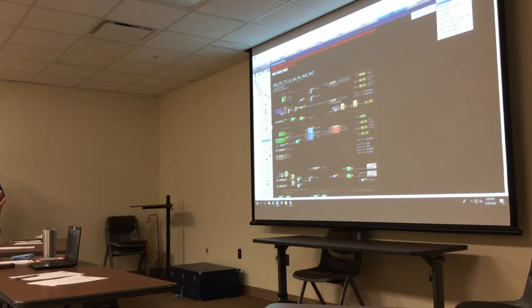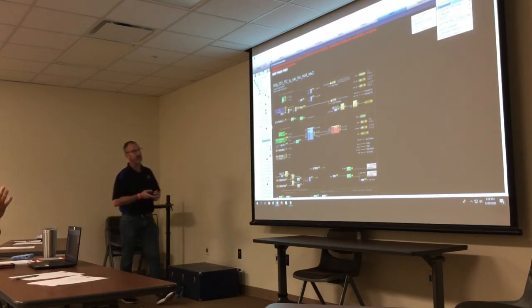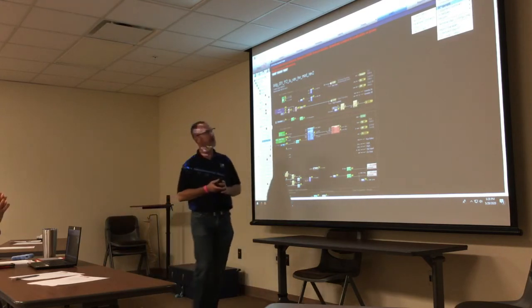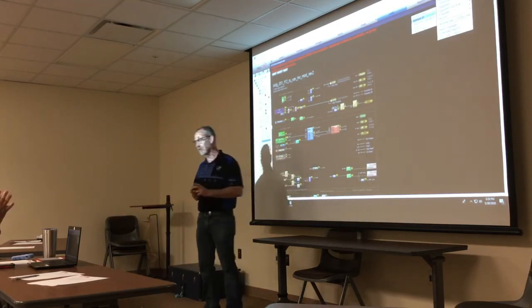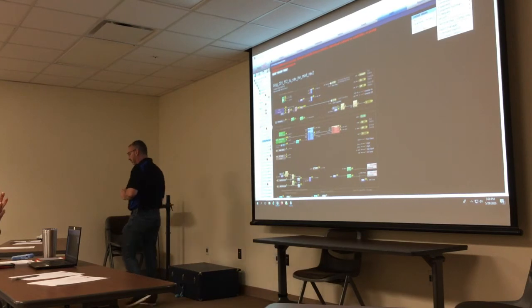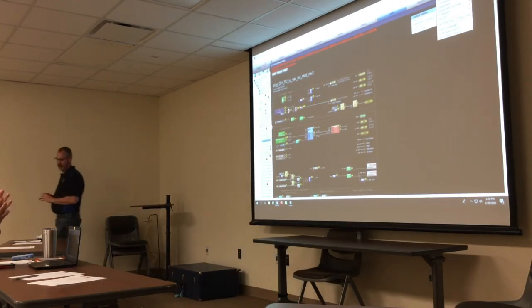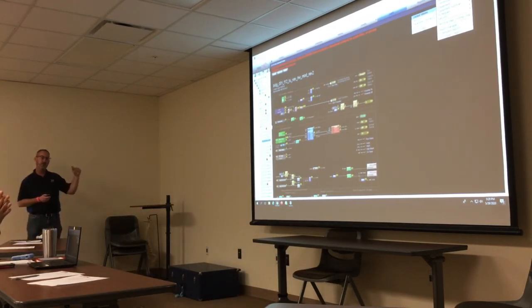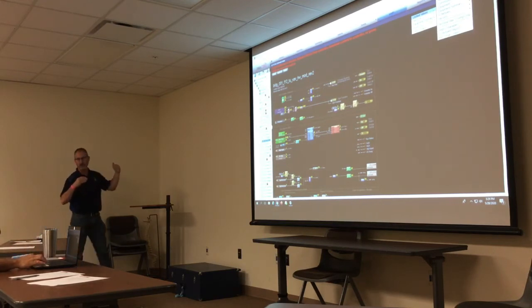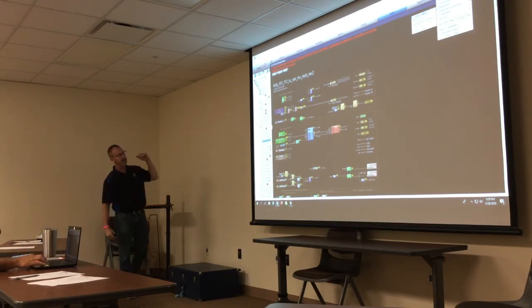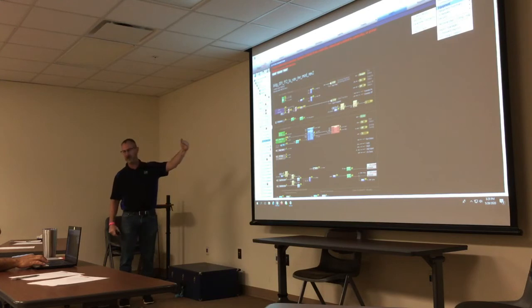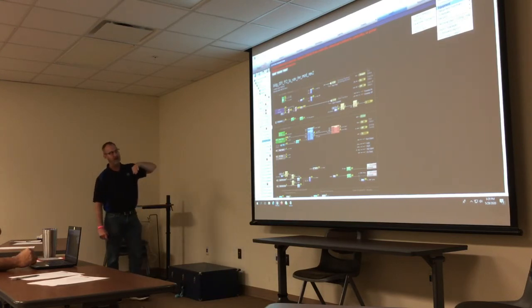Okay, equipment. Probably the best report for you to run on a regular schedule is the locked value report. So if you run that once or twice a week on a schedule, you can see who and what is locked in your system. In other words, if somebody overrode the cooling tower fans to 100%, they've locked them - you can get that information out of a locked value report.